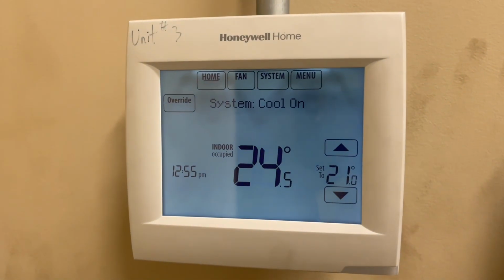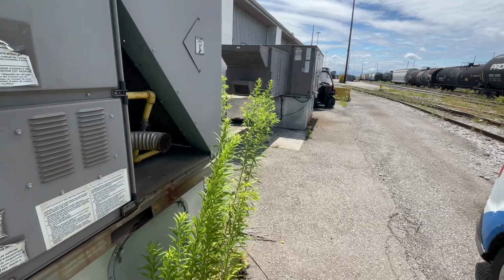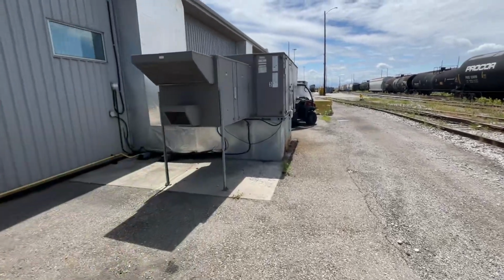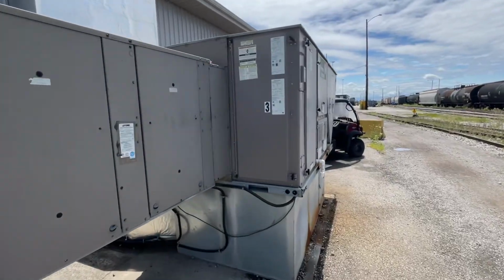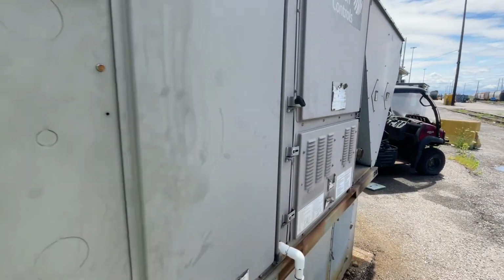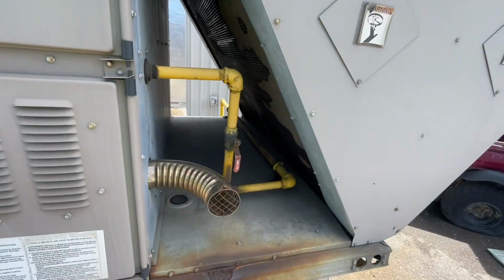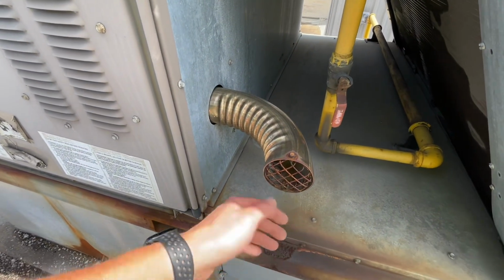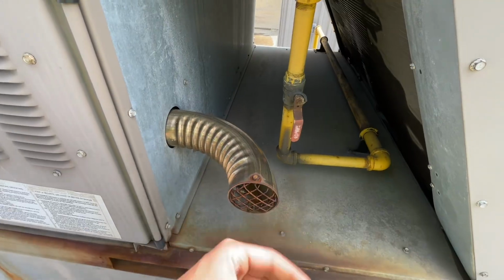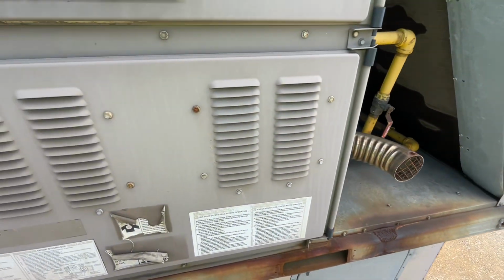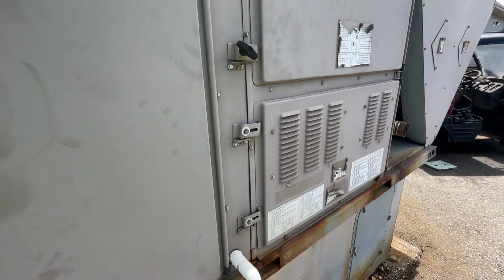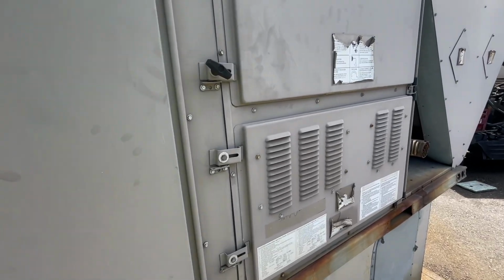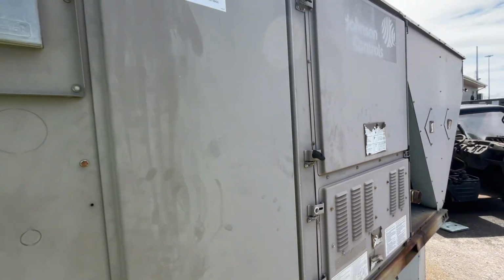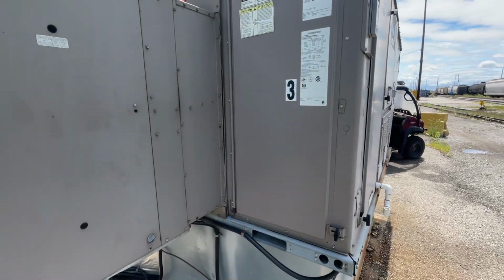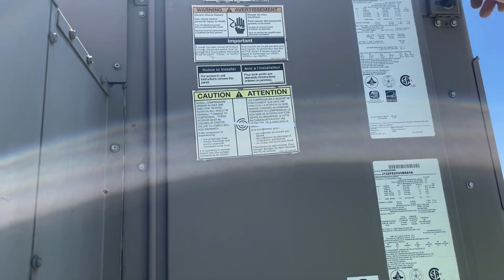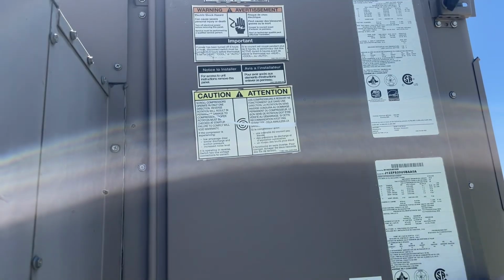Let's go out to the rooftop and we'll take a peek. Unit 3. All right, rooftop 3. I believe this is his second feature on my channel. First impressions, yeah, that's not good. Our inducer motor is running with a call for cooling. So just from experience, I'm going to assume that the rollout's open, maybe the high limit. Let's open this up and see what we find. All right, let's open up this electrical panel door, see what our board's saying.